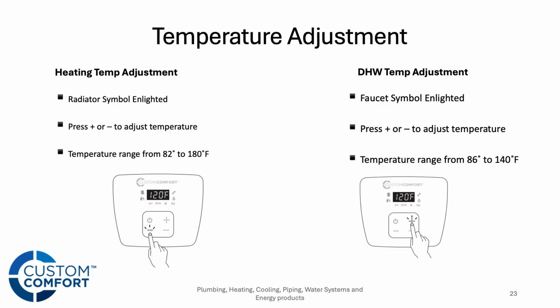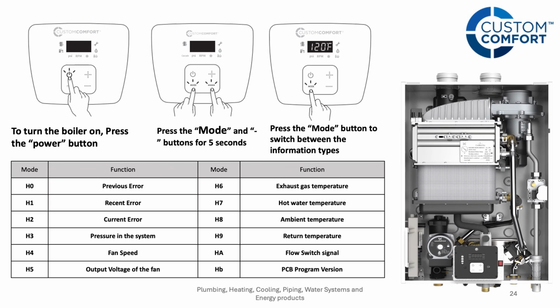That's the homeowner side of things. If a homeowner were to play with this boiler, that's all they're going to have access to. If we want to get into the installer mode, we can do that, and it's a little trickier to keep homeowners out of it. That's the mode and minus buttons held for 5 seconds to get into the advanced parameters on the control. That is where you're going to find the 3 previous errors that the boiler and control will provide. So if it ends up being a problematic job, we give you the 3 previous errors. Again, those are only visible and available in the installer mode.